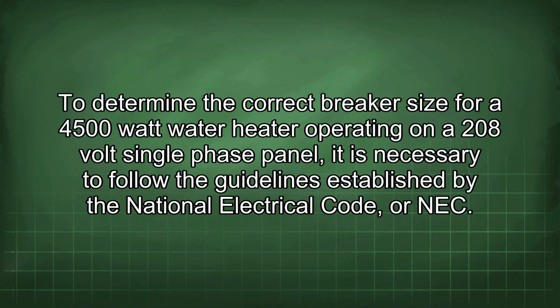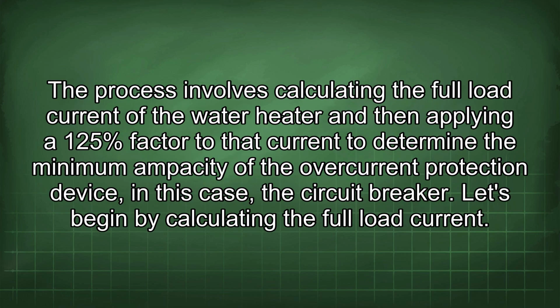To determine the correct breaker size for a 4500 watt water heater operating on a 208 volt single-phase panel, it is necessary to follow the guidelines established by the National Electrical Code, or NEC. The process involves calculating the full load current of the water heater and then applying a 125% factor to that current to determine the minimum ampacity of the overcurrent protection device, in this case, the circuit breaker. Let's begin by calculating the full load current.